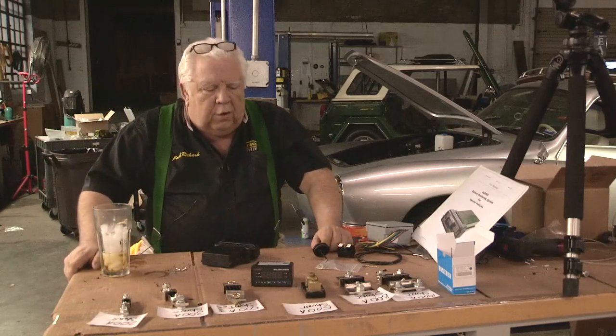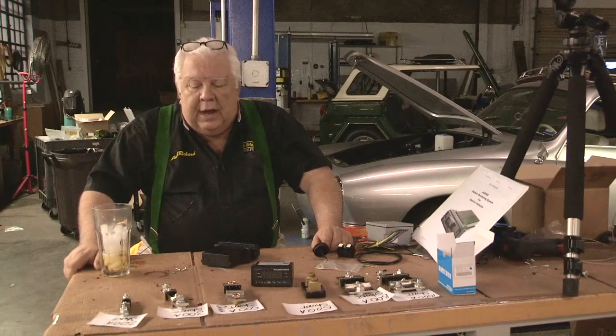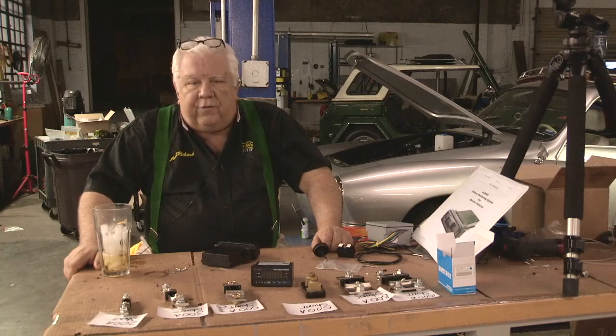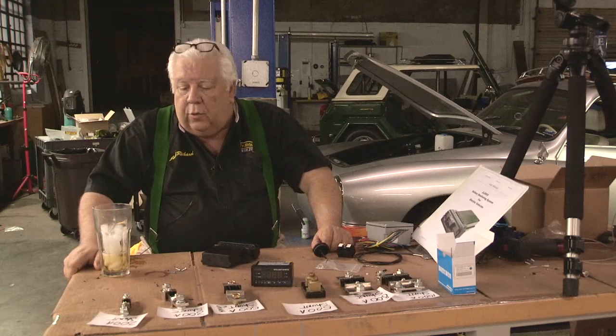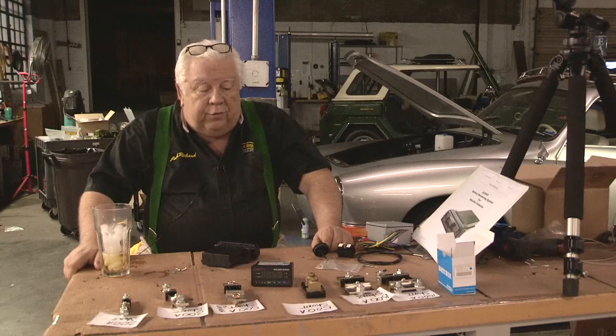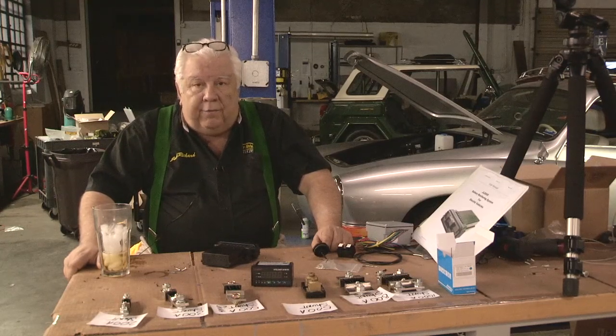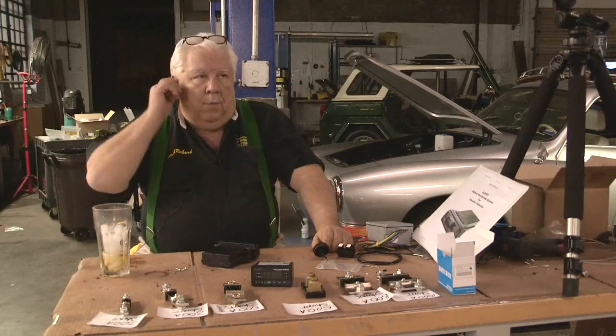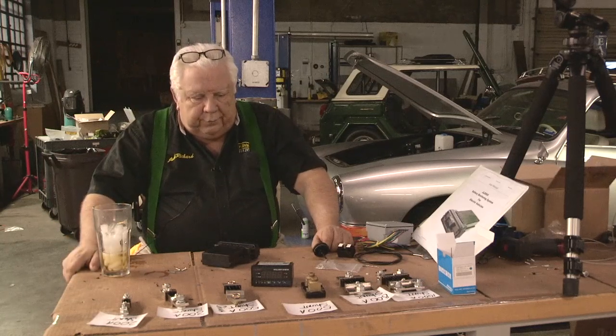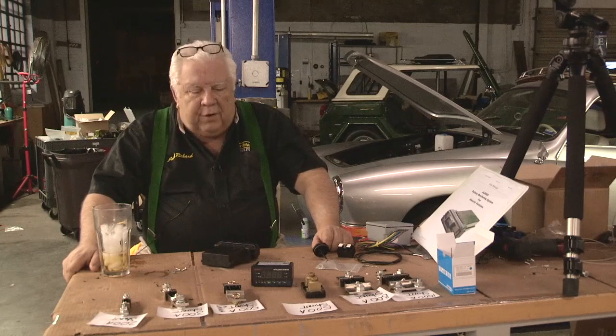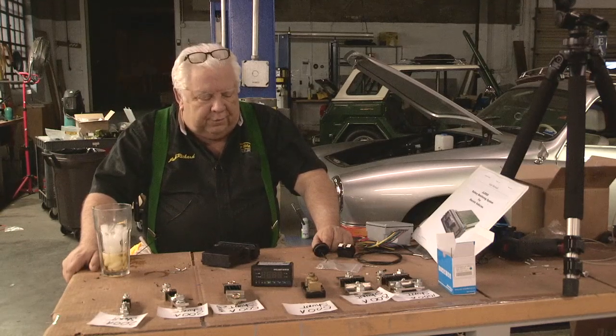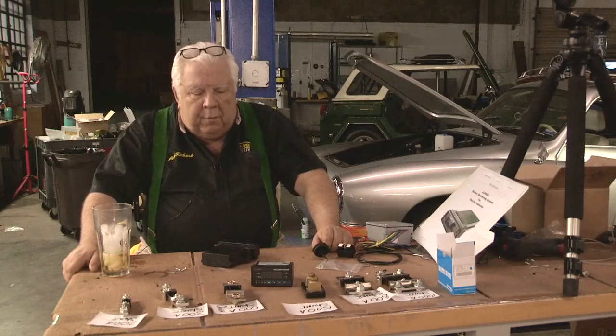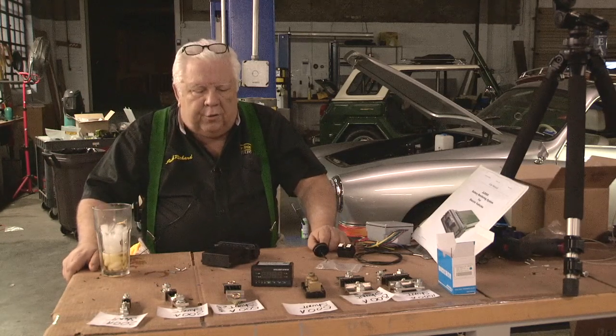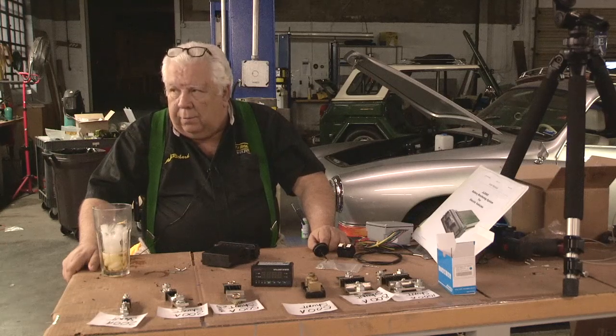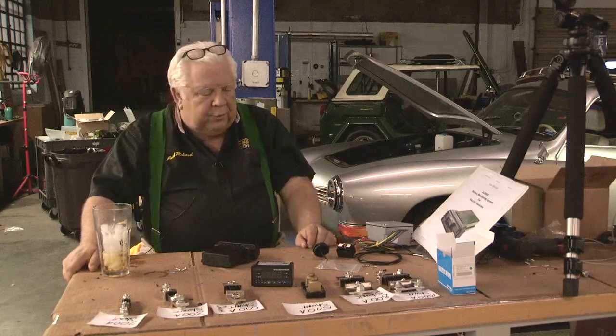And so those are the 3 parameters on shunts. And what the current actually is, it's not a limit, it's part of a ratio. 500 amps to 50 millivolts, 400 amps to 100 millivolts, 200 amps to 75 millivolts. And to get the resistance is very easy. You divide the 50 millivolts by 500 amps, and you get 0.0001 ohms. And I may have that plus or minus a couple of zeros, but a very small amount of resistance, which is what we want, but a very accurate level of resistance. So when we measure 10 millivolts through there, we know that's going to be exactly 100 amperes. And if we go to 9.9, that's going to be 99 amperes. And that's how current measurement works.